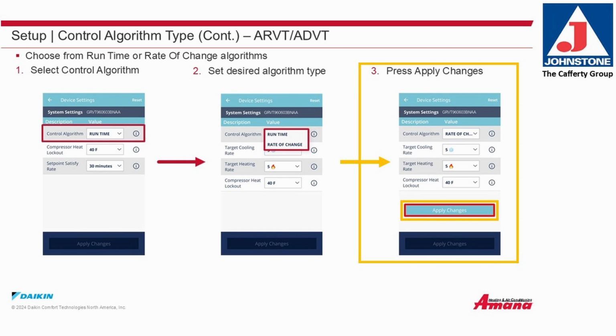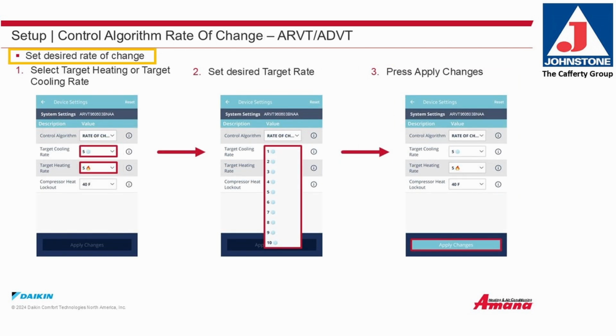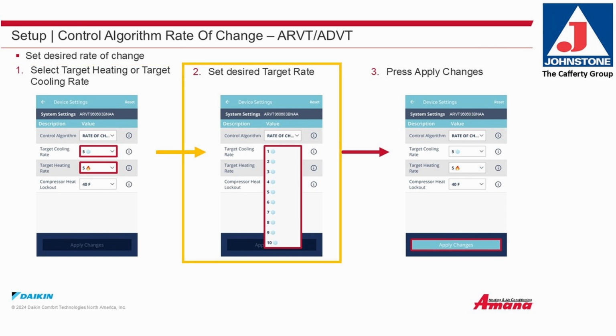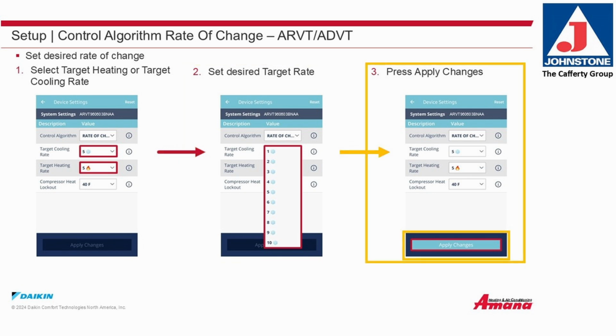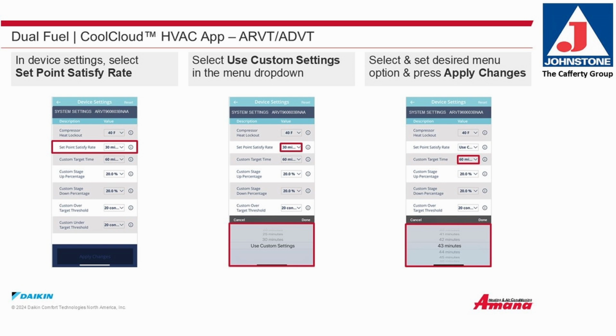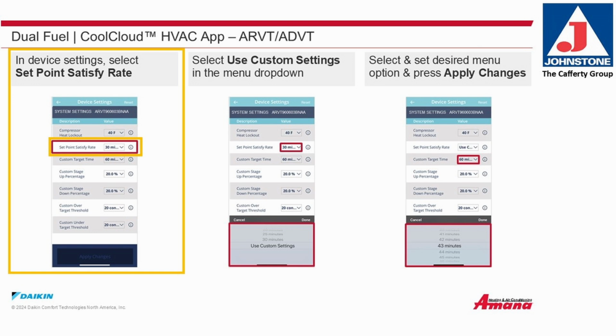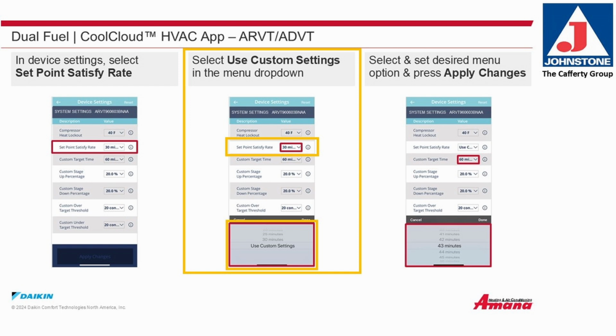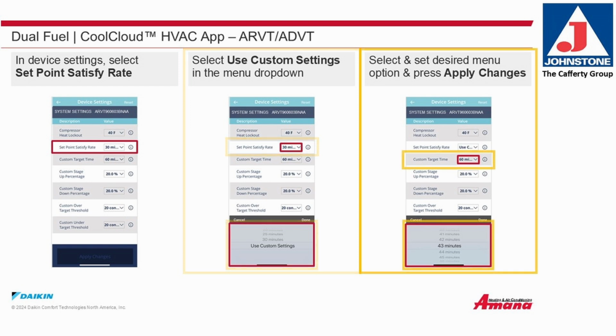To set up the control algorithm rate of change, set the desired rate of change. Select the target heating or target cooling rate. Set the desired target rate. Press Apply Changes to save your selection. Dual fuel using the CoolCloud HVAC app. In the device settings, select Set Point Satisfy Rate. Select Use Custom Settings in the drop-down menu. Then select and set desired menu options and press Apply Changes.